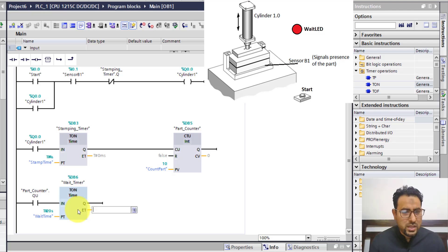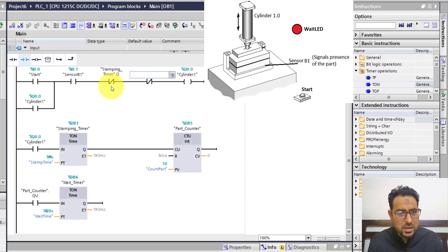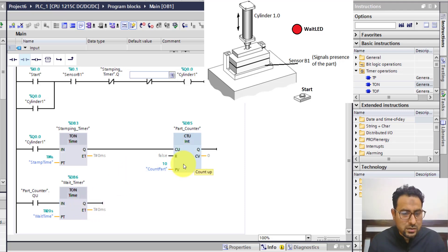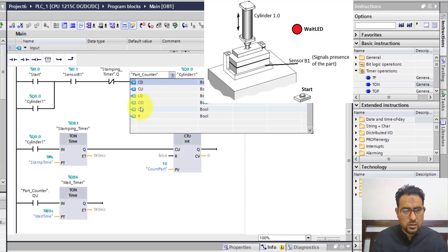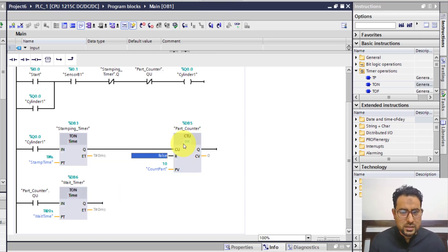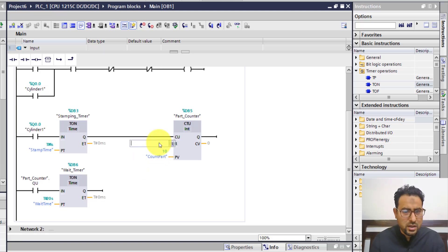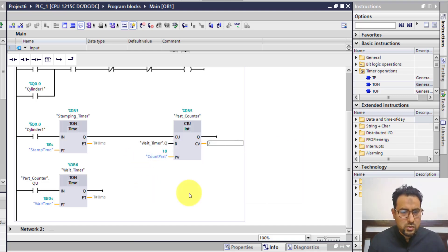Once this timer is done, only then can the system be used again. I'm inserting a normally closed switch that will disconnect cylinder 1 from power for as long as this timer is timing. After this timer completes, I'm going to reset the counter. The part counter's Q-bit remains high while the timer is timing, and when the wait timer's done bit goes high, it will reset the counter via the reset pin.